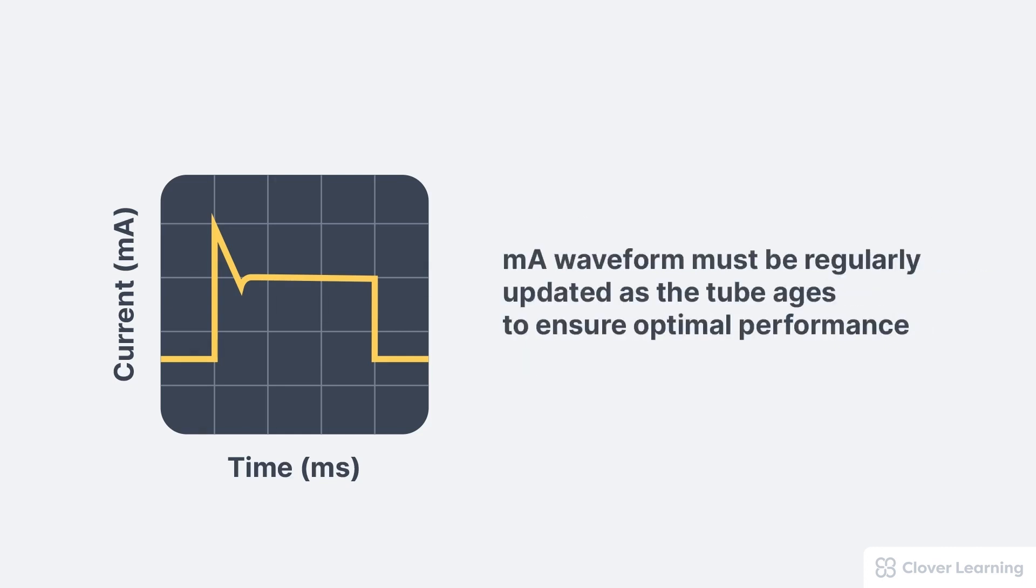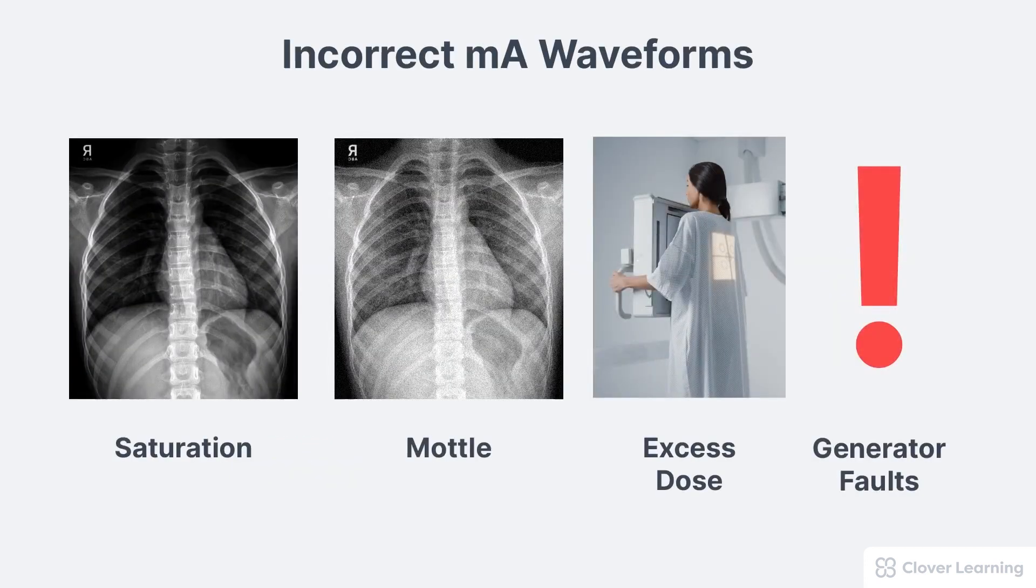Also, the MA waveform must be regularly updated as the tube ages to ensure accurate and optimal system performance. This is because the x-ray tube properties can change over time. Just like KV, incorrect MA waveforms can result in several adverse effects, including image quality issues, unnecessary patient dose, and generator faults.